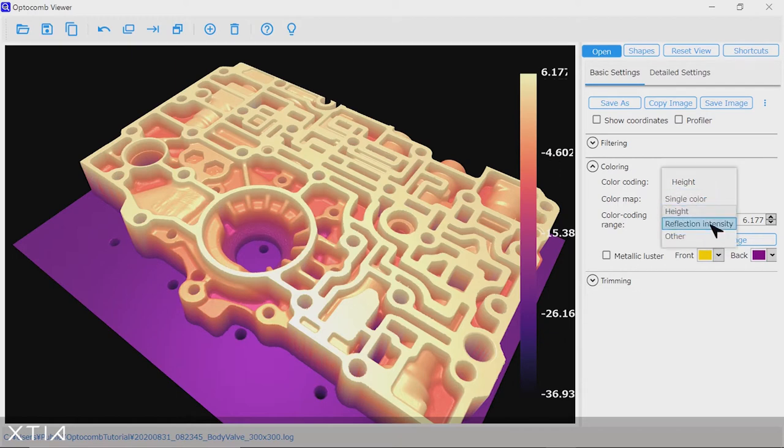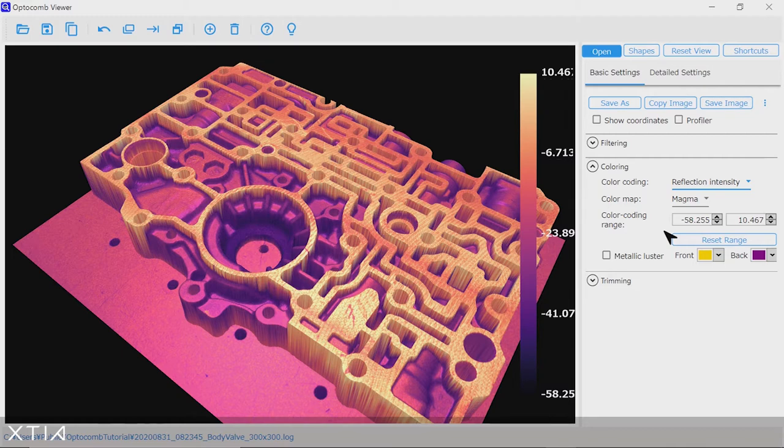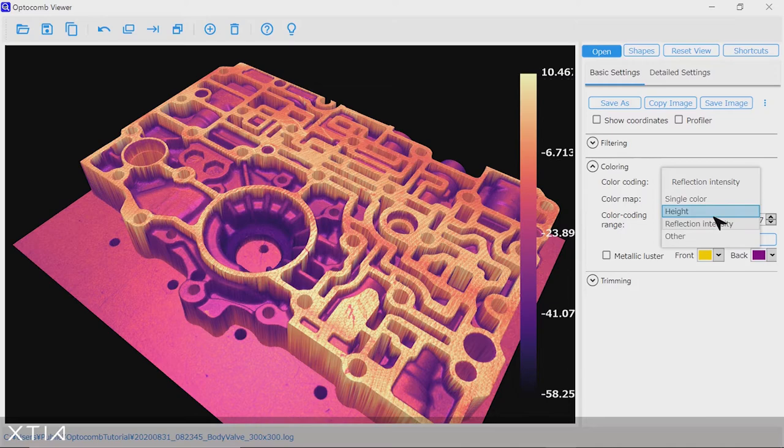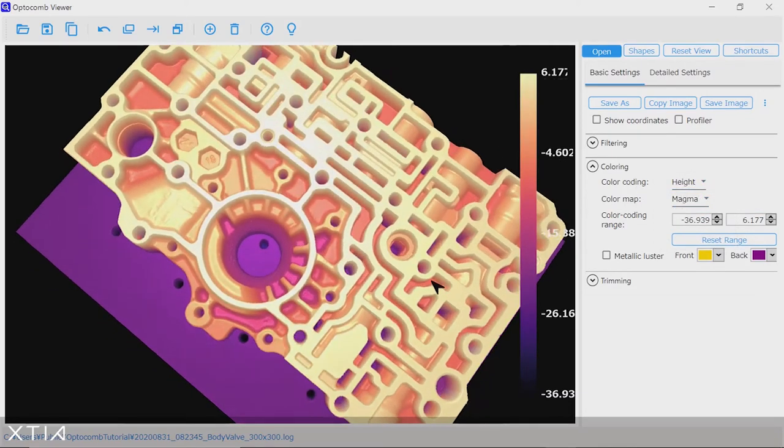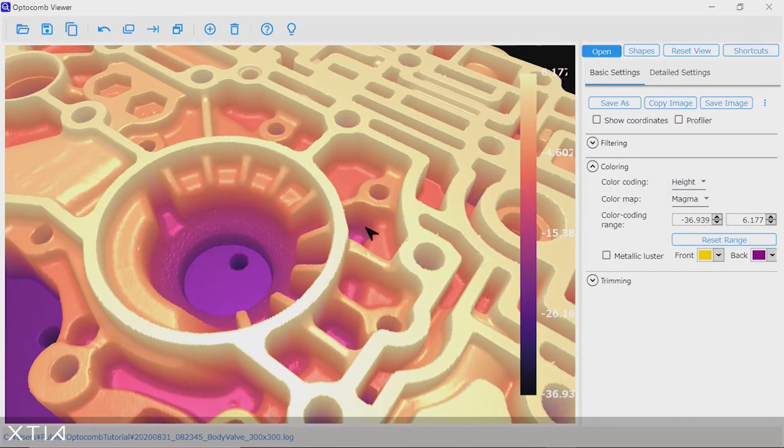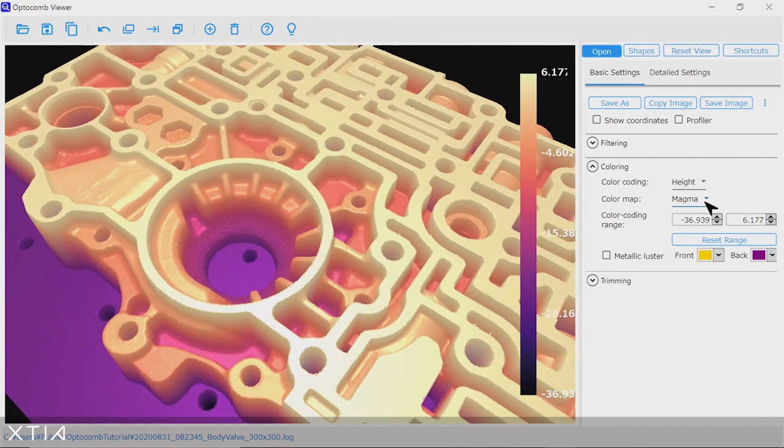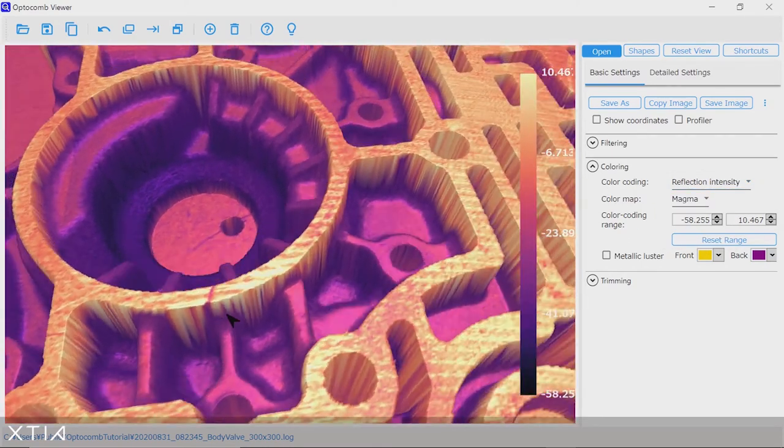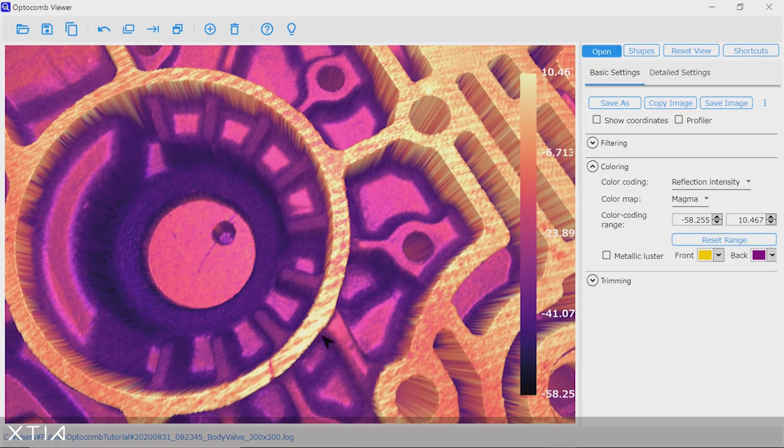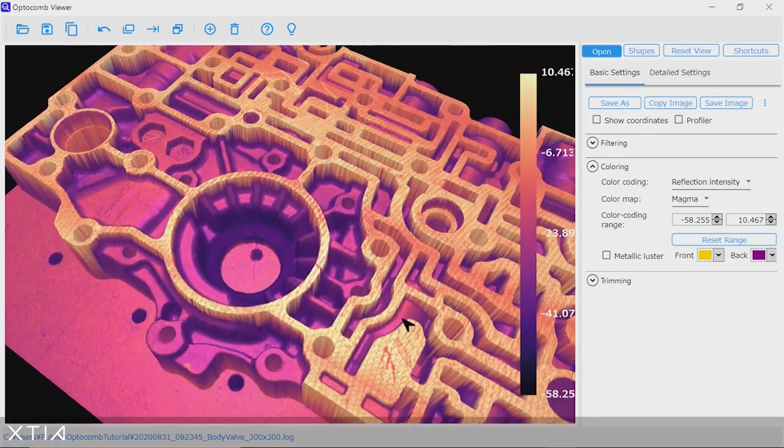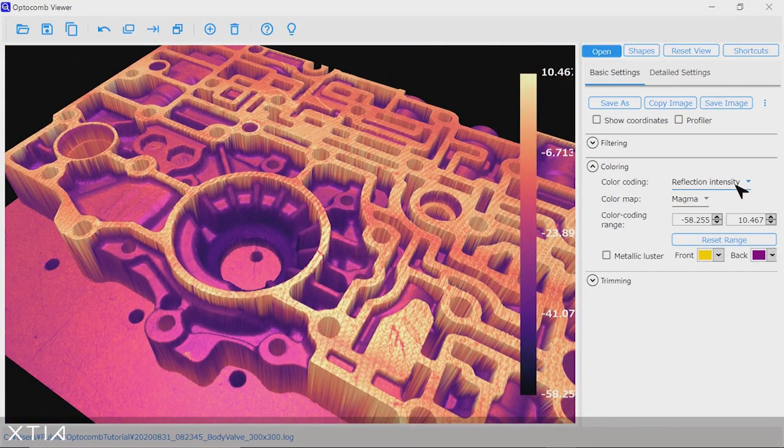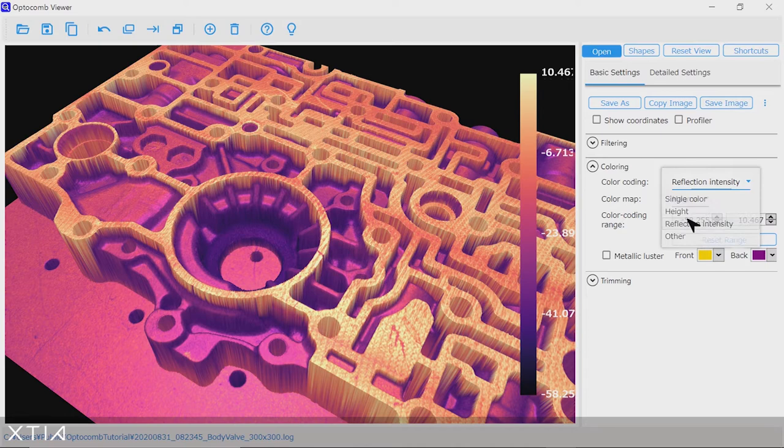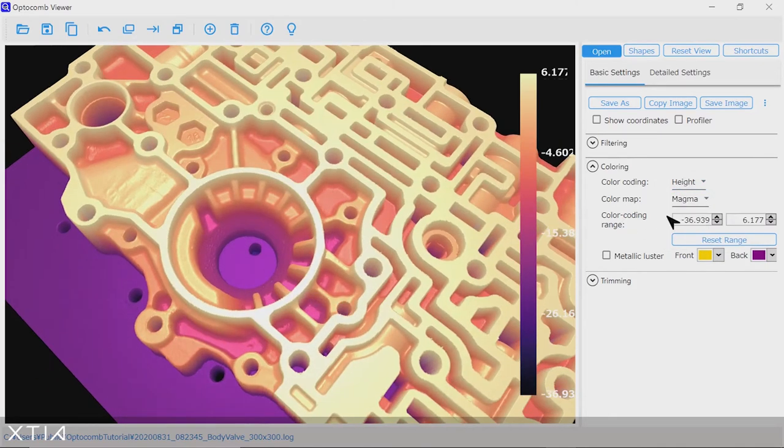More importantly, you can choose what data is displayed. So by default, the color scheme reflects the height of each point of the valve body. But the color scale can also show the intensity of the Optocomb light reflected on the valve body surface. In this case, the Optocomb Viewer shows both a superposition of the height data and the intensity data, which can be very useful in order to confirm the presence of surface defects that have neither height nor depth.